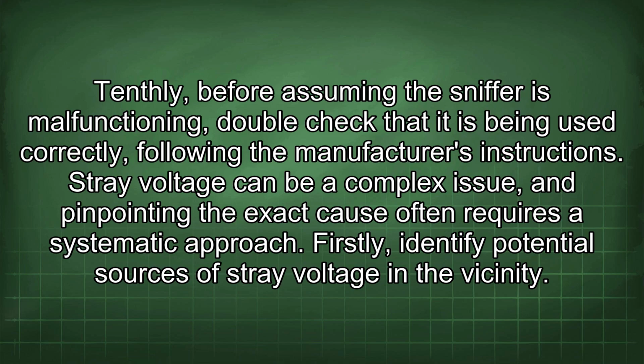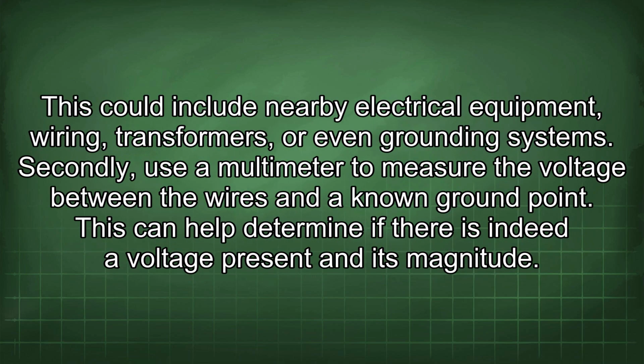Firstly, identify potential sources of stray voltage in the vicinity. This could include nearby electrical equipment, wiring, transformers, or even grounding systems. Secondly, use a multimeter to measure the voltage between the wires and a known ground point. This can help determine if there is indeed a voltage present and its magnitude.